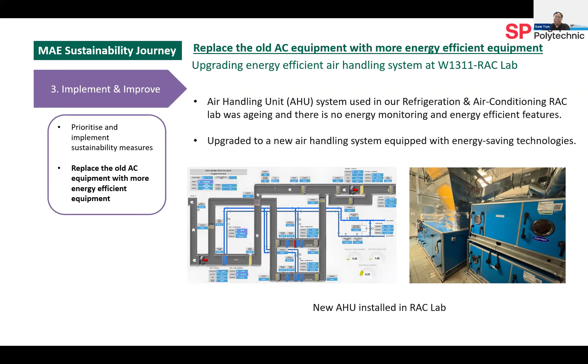I would like to highlight the same equation again here, the 2 key factors: equipment efficiency and cooling load. In our case, for this upgrade, only the airside system is upgraded and there is no change to the water side of the air conditioning system. As a result, overall system efficiency actually did not improve. In fact, it has declined.